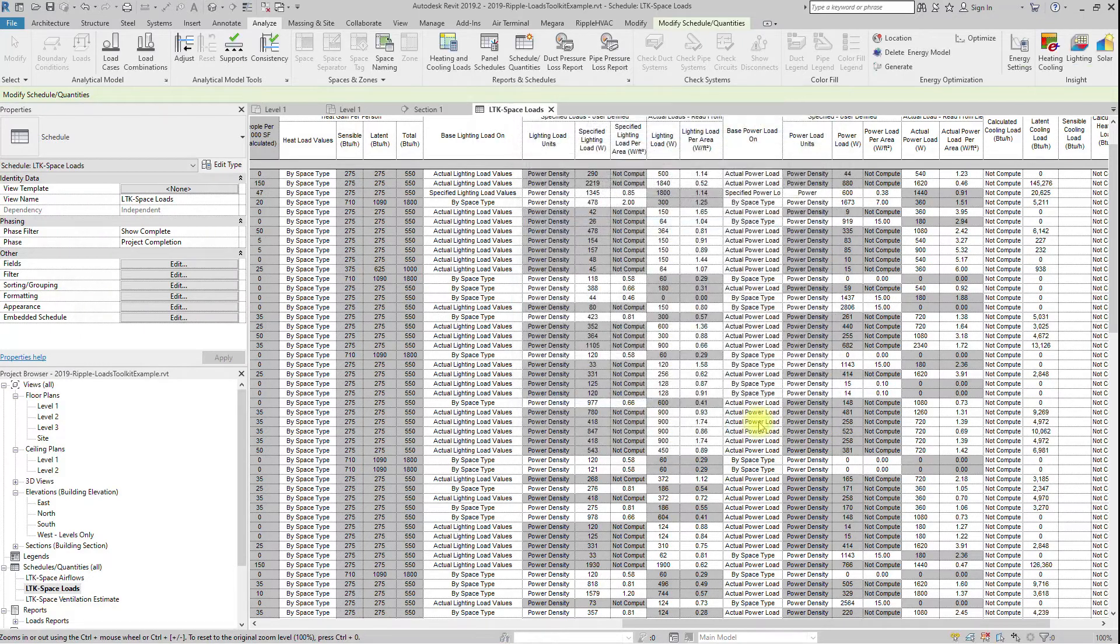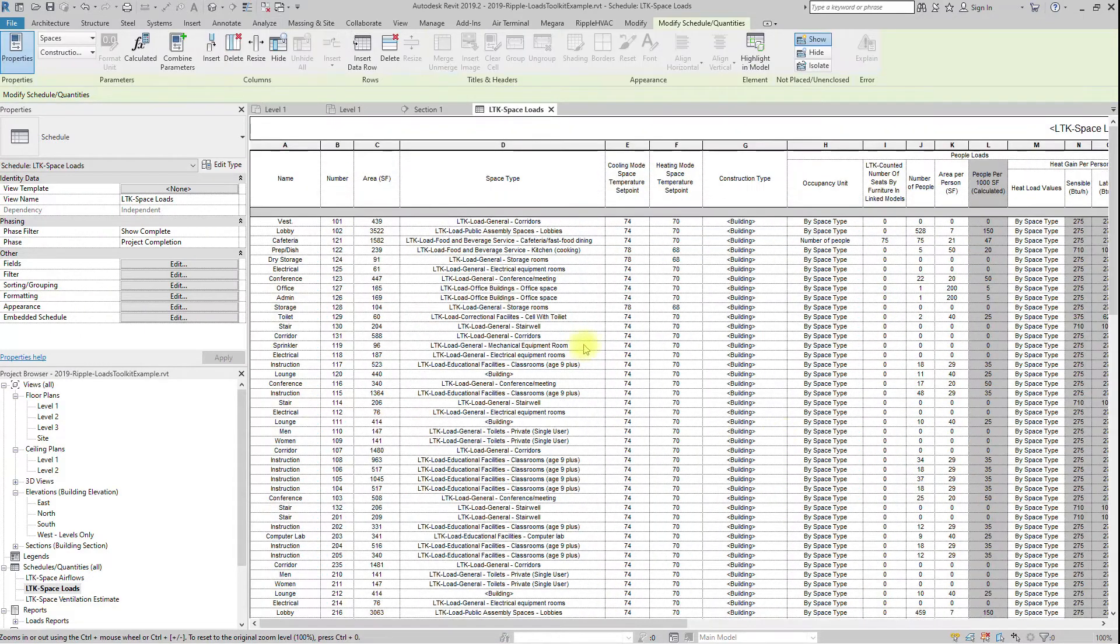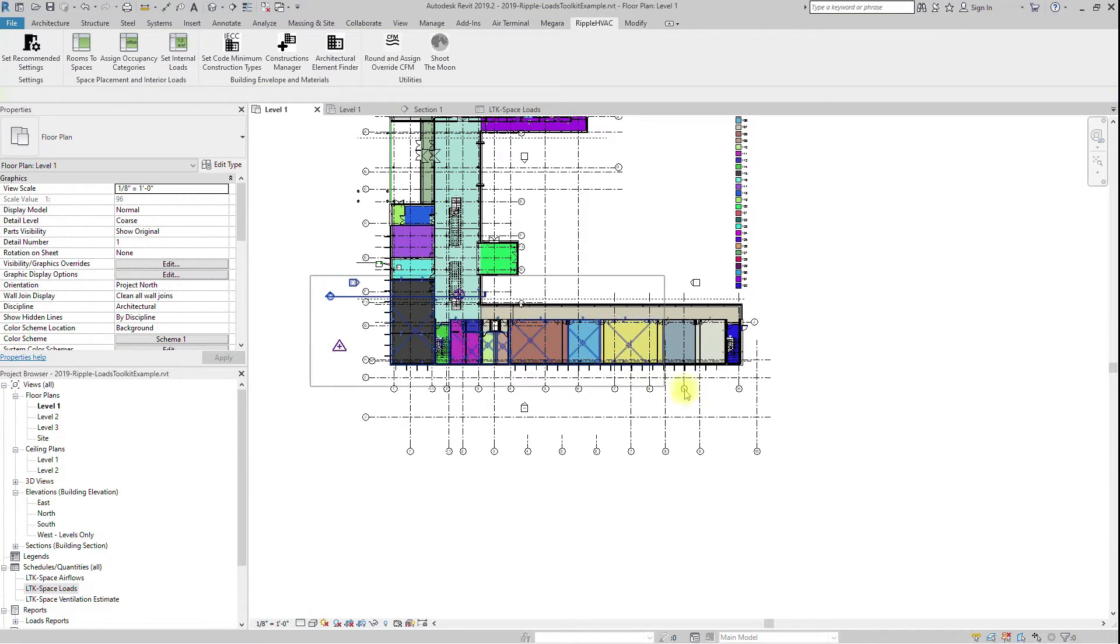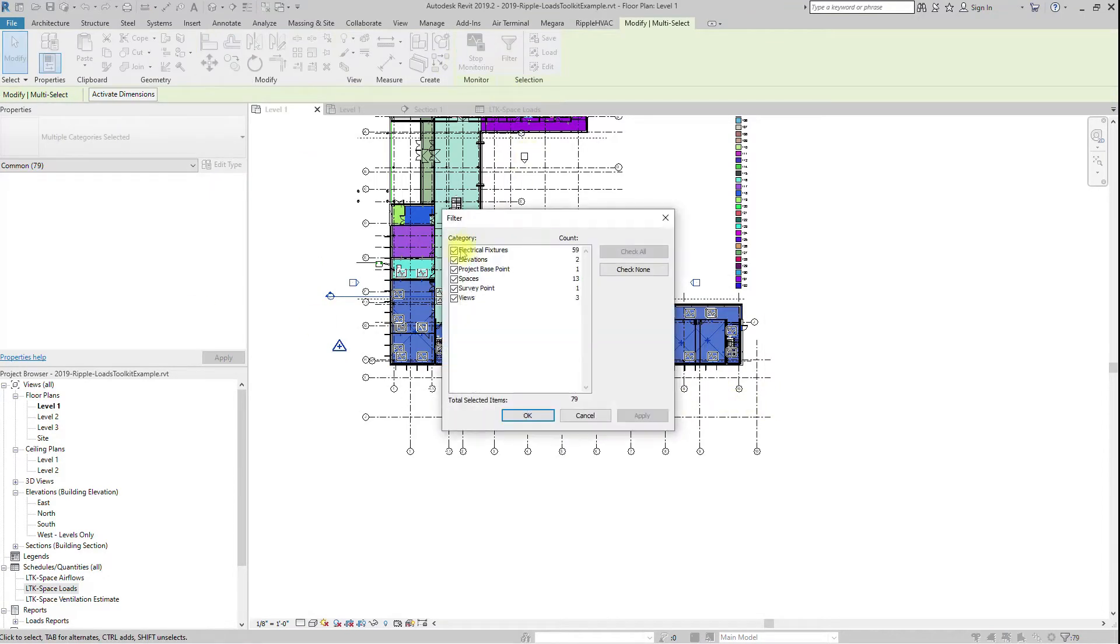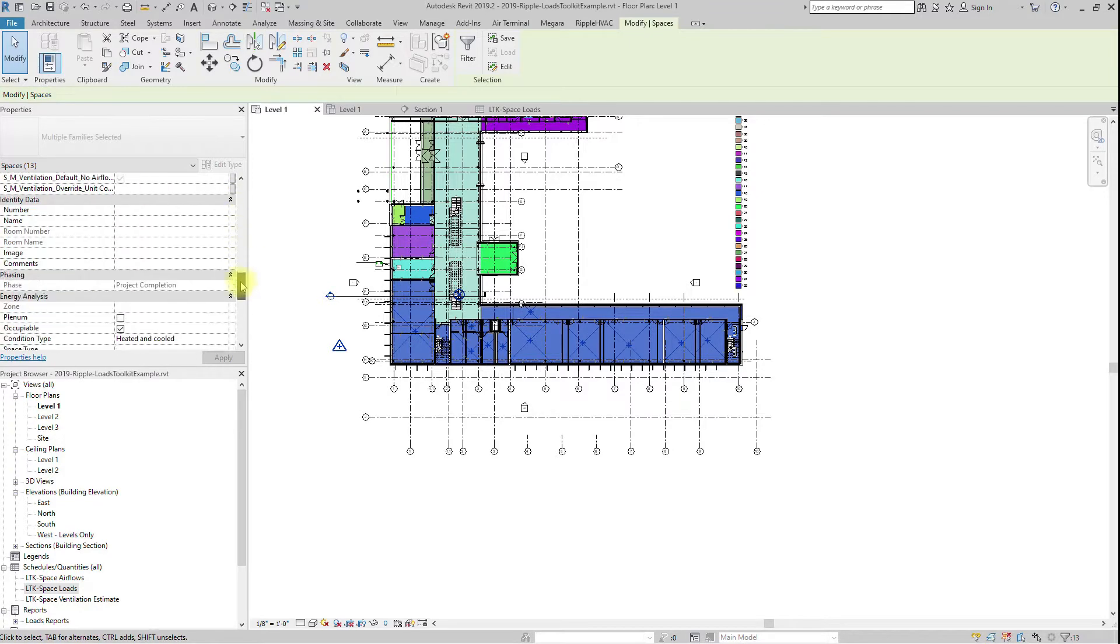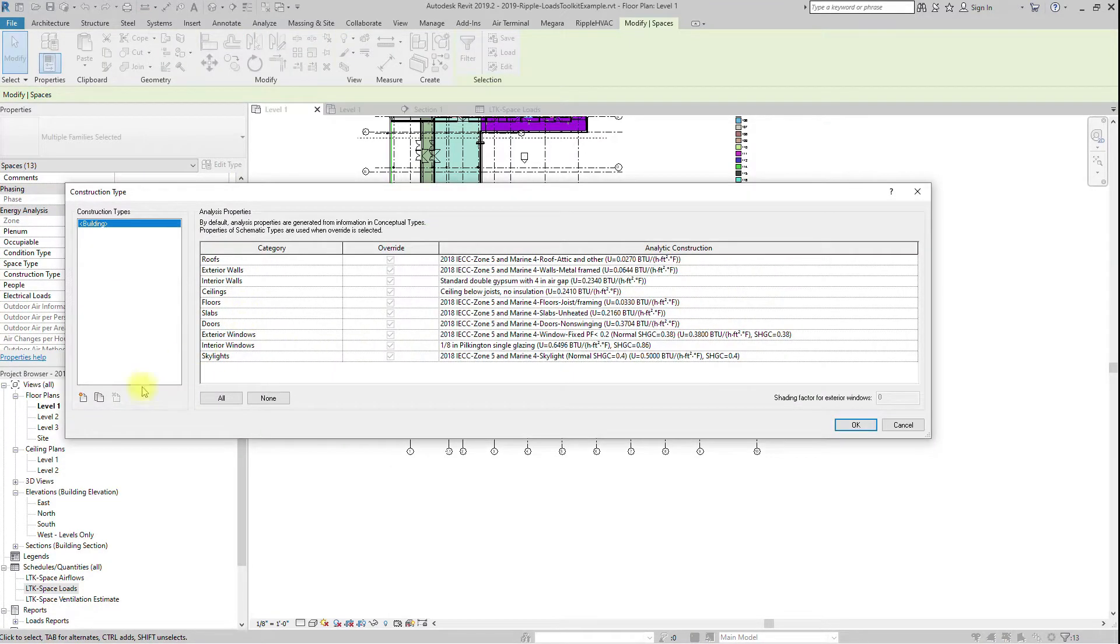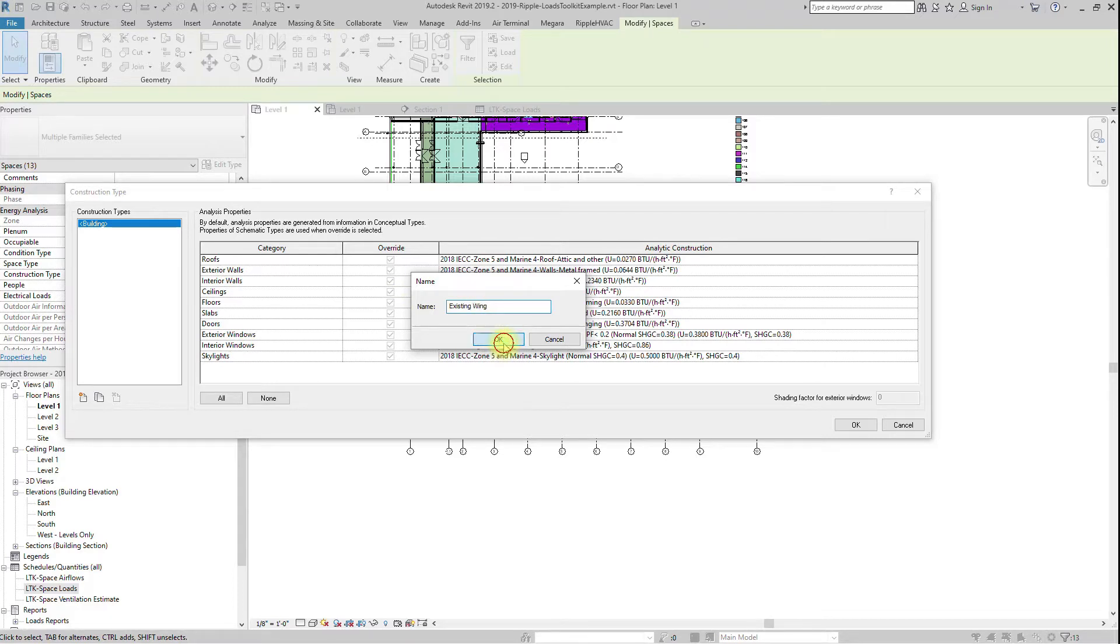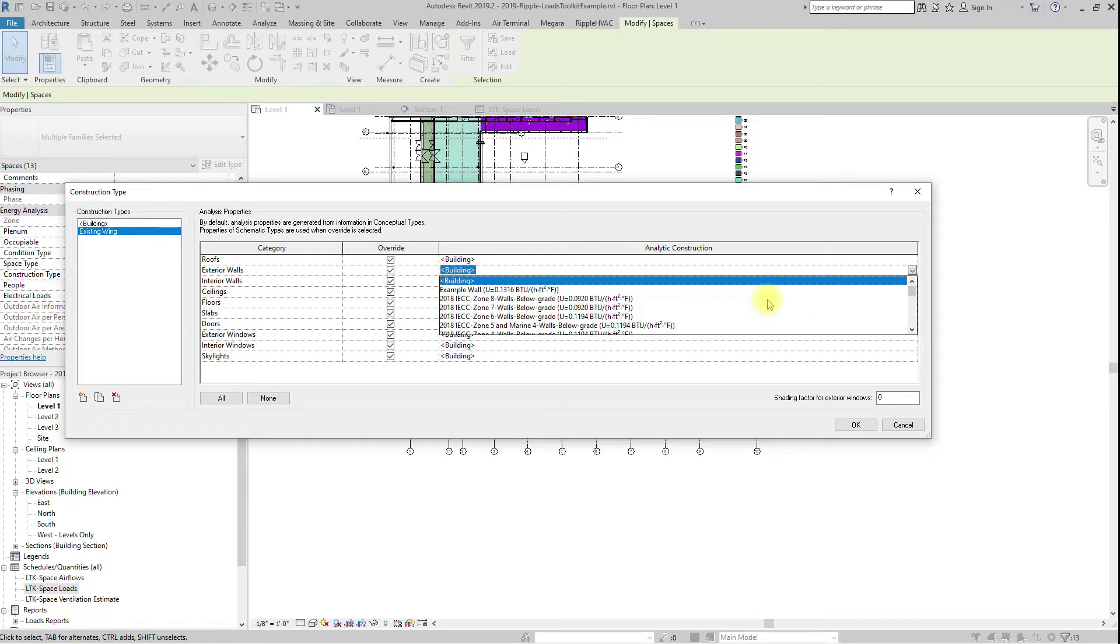Thermal properties can also be overridden on a space-by-space basis. For example, if you have an addition to an existing building, and the addition will be code minimum, but the existing building will be something less than that, you can create a new construction type, set the override thermal properties appropriately, and then assign it to the construction type space parameter of all the spaces in the existing building.